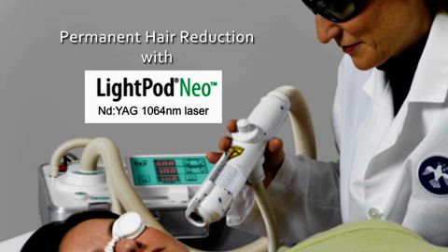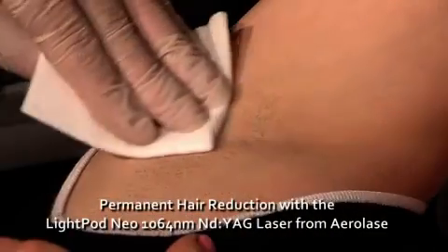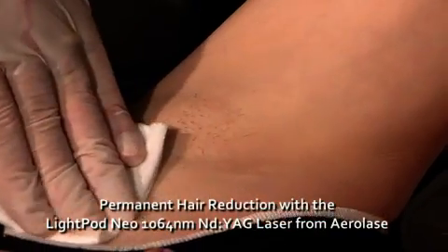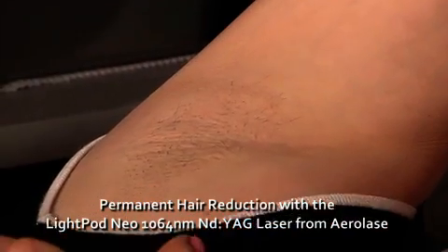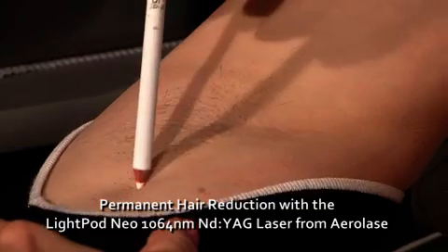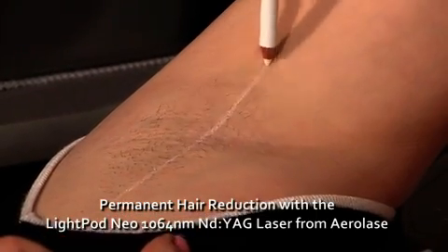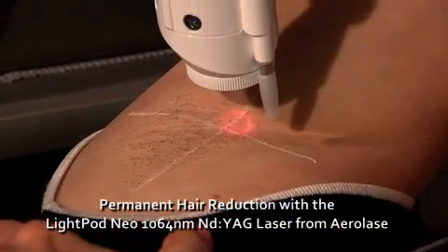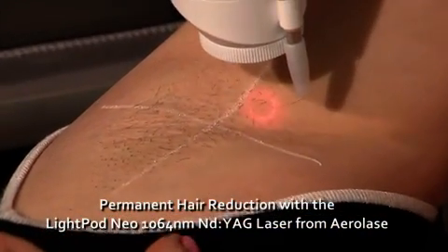Permanent hair reduction is one of the most common uses of the LightPod Neo Laser from Aerolase. The patient should present with short stubs of hair or about three to four days of growth. After wiping the treatment site to ensure the skin surface is clean and dry, the site is marked off with a light-colored pencil so that the pencil markings do not absorb any of the laser energy. The red aiming beam is focused upon the site and the pulses are delivered in rows to cover the area.